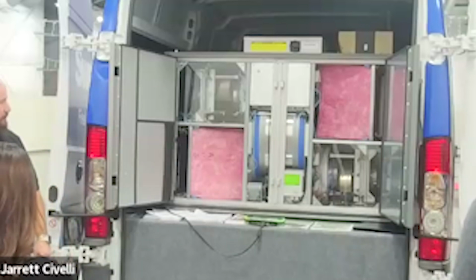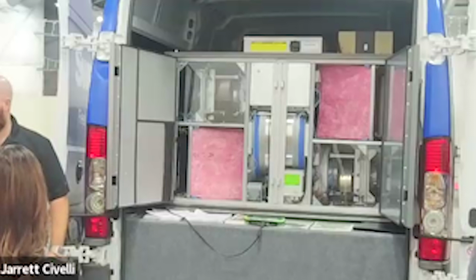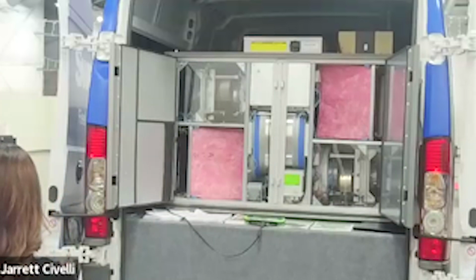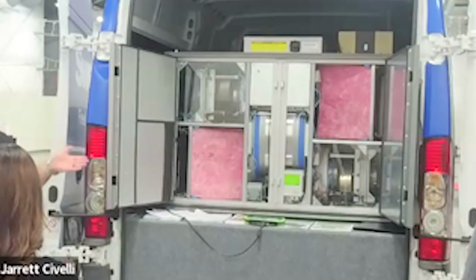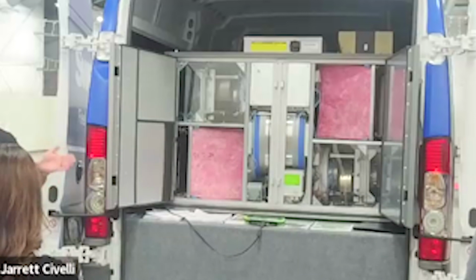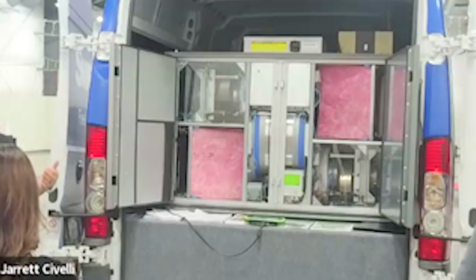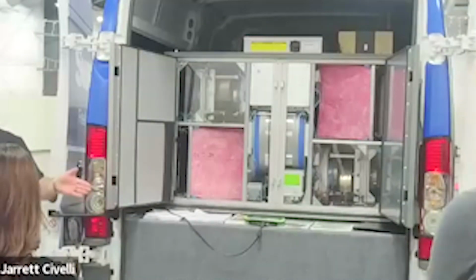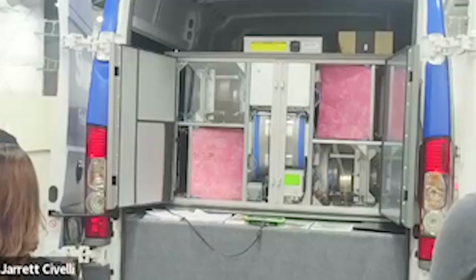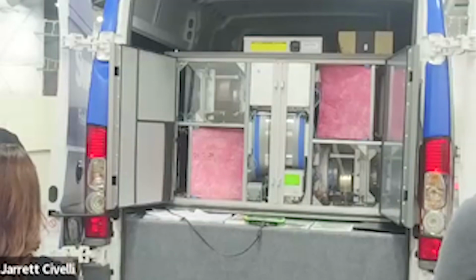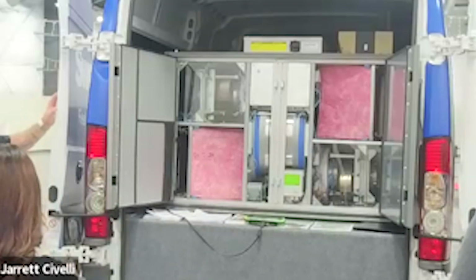That's very rare. So this has a sensor, it'll tell you when to clean the filters. The filters are pretty awesome on this one. Each time you change the filters and when you start up the unit, you calibrate the differential pressure across it. Then it tracks that and tells you when the filters are dirty. When you put in a new set of filters, you recalibrate that sensor. So you're looking at real-time filter loading as opposed to just a switch that's been set at 1.5 inches of water column.